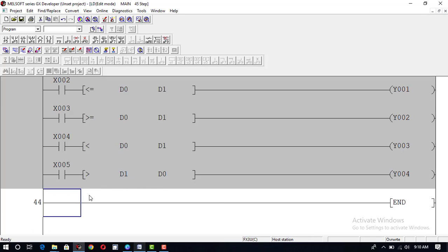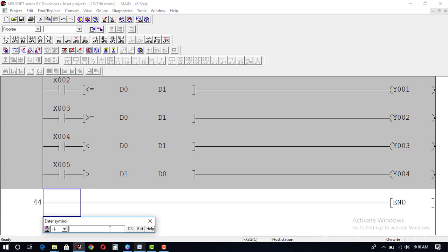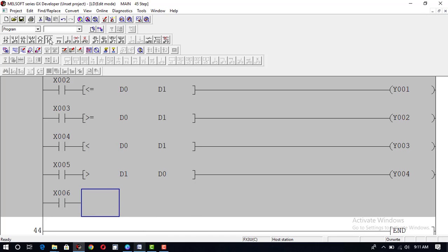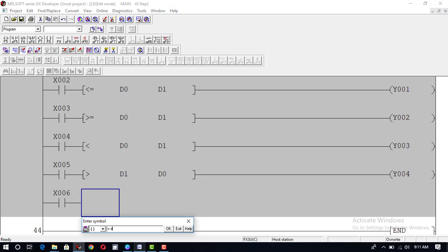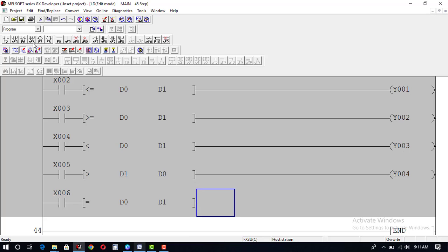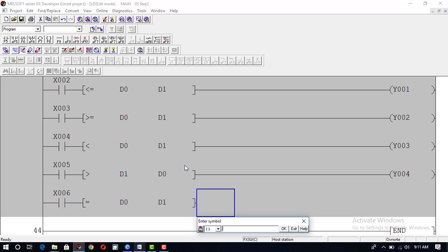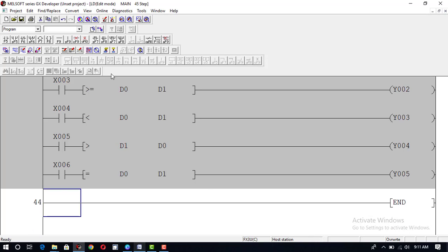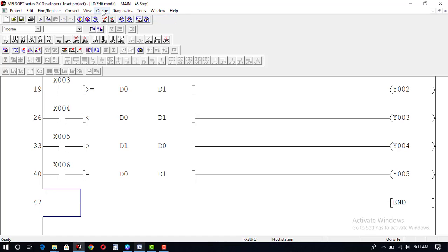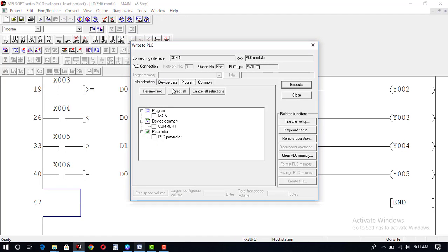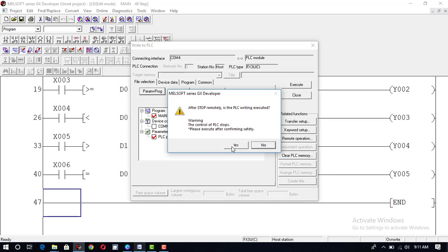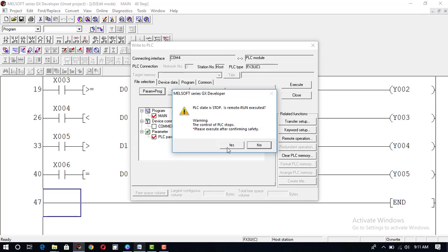We can also use the equal to sign for comparison. Taking input x6, we use the equal to instruction to compare d0 and d1. When these two values are equal, the output y5 will be turned on. We now convert and write this program to PLC — program plus parameter, execute, write to PLC. The remote run is executed and the PLC is ready.